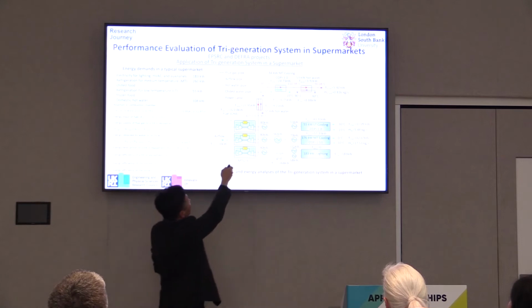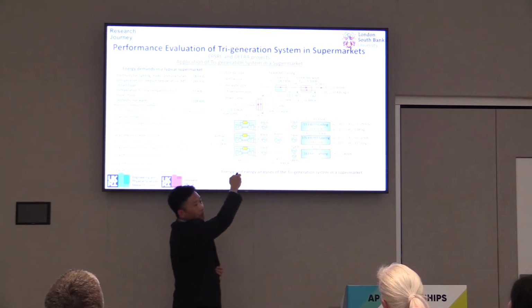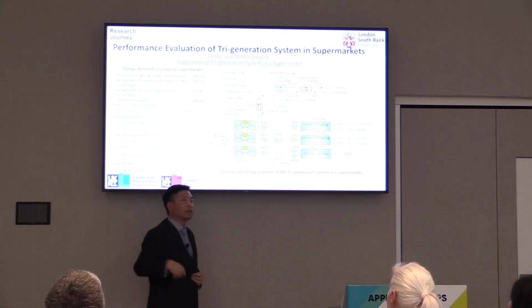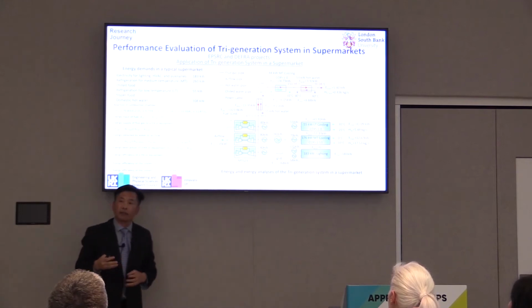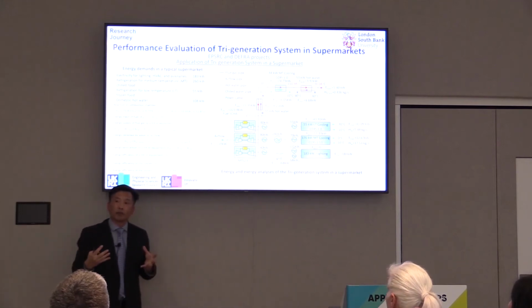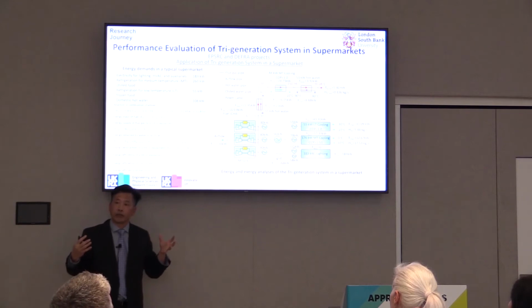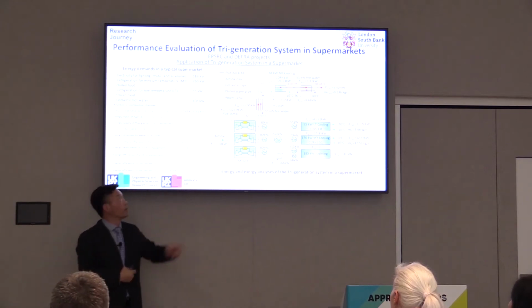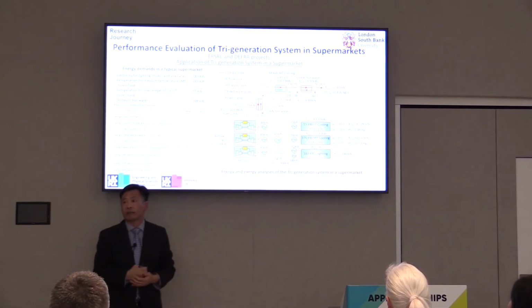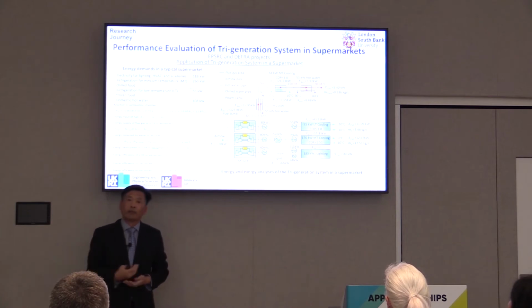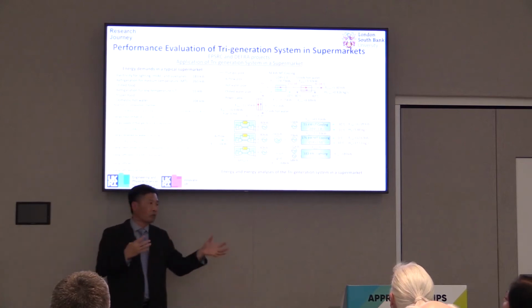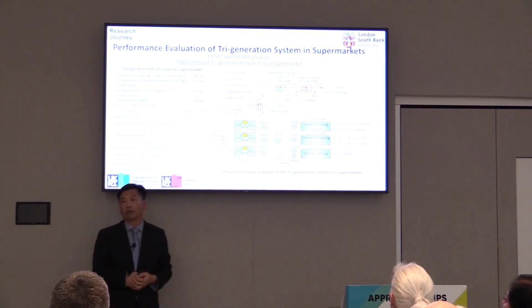So this is something you need to think about redesigning. Instead of heating the hot water directly, maybe you think about another way to produce electricity first, because the temperature is high enough that it can be used to produce electricity. Like the gas boiler, using the combustion gas to heat the hot water, actually the efficiency is quite low.